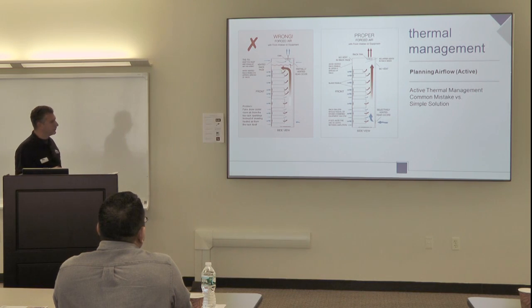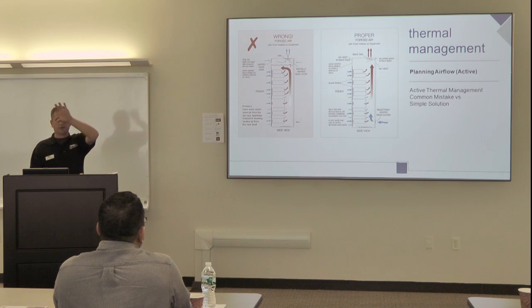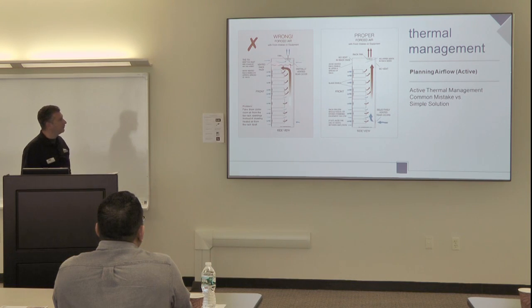You see a lot of the racks out on the marketplace actually have vents at the top because they're designed for convection. When you go to put a fan on top, you want to make sure you block that top vent off, because otherwise you're just causing cool air to circulate up there, and the hot air can't get through. So basically the hot air is staying within the rack. The proper way is to block the vents off over the top third of the rack or so, so you can start that hot air with the fan. It'll pull the hot air right out, giving you a nice chimney effect outside the rack.